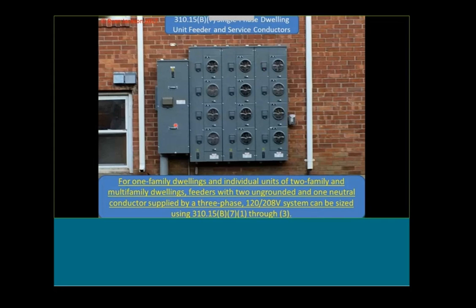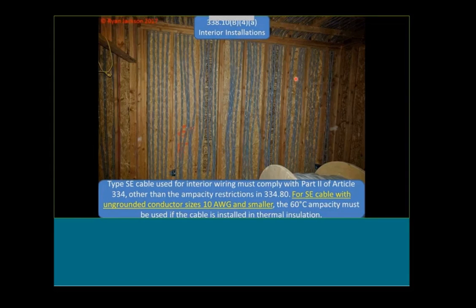So now, if this is a three-phase service, I can actually use smaller wires coming out of each of these breakers. That's a significant cost difference, especially when you couple it with another change we made in 2017, in Article 338. Article 338 talks about SE cables—all of these gray cables going through here. I'm guessing this is maybe a four-story apartment building.